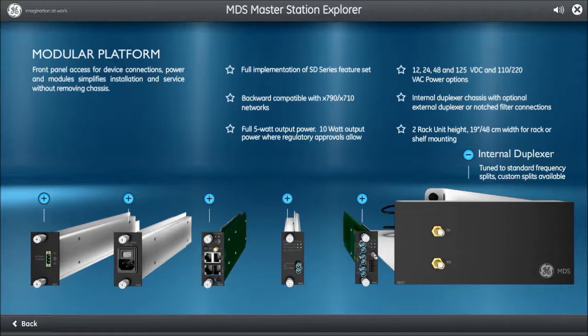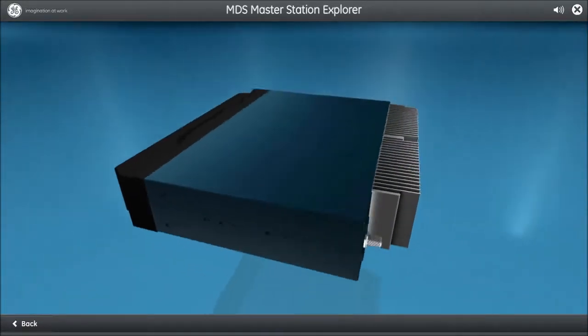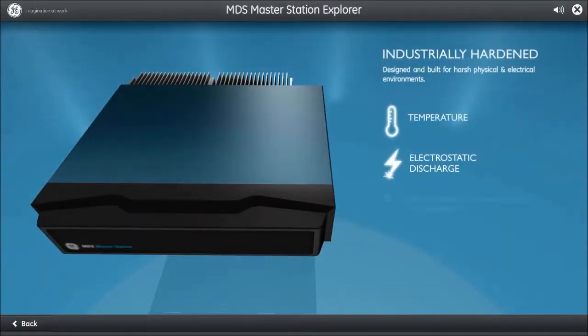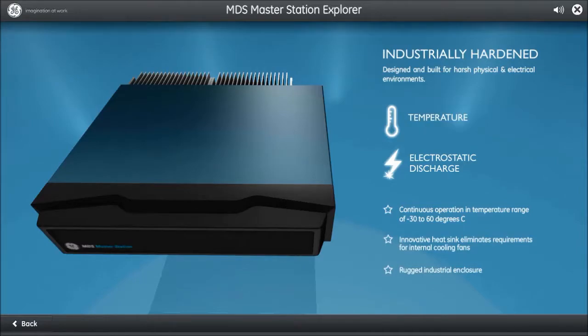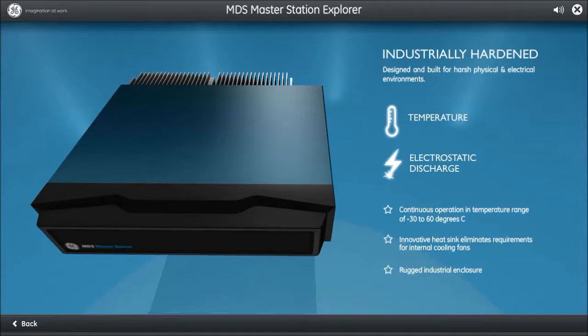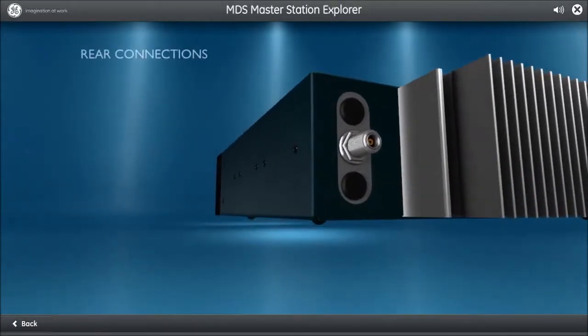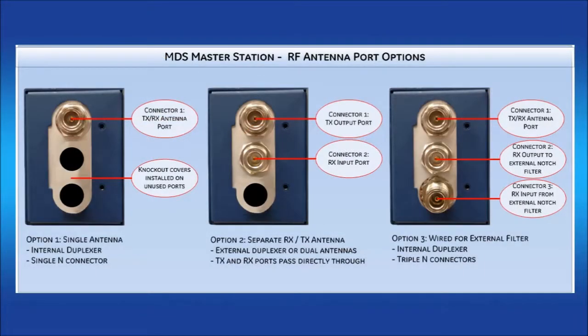The antenna and external filter connections are found on the rear of the unit. The MDS Master Station is industrial rated, verified to operate at an extreme temperature range of minus 30 to plus 60 degrees Celsius, and can withstand electrostatic discharge. The unit has an innovative heat sink, eliminating the need for a fan and removing the chance of overheating. The back of the unit contains receive and transmit RF connectors. There are three options when ordering: Option 1 uses a single N connector with an internal duplexer; Option 2 separates TX and RX into two N connectors for connection to an external duplexer; Option 3 has the internal duplexer and triple N connectors to allow connection of an external notch filter. Knockout covers are installed on unused ports.